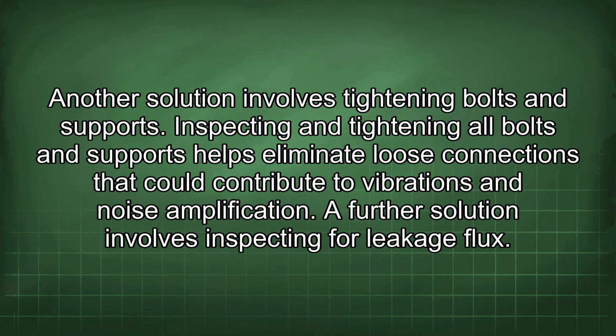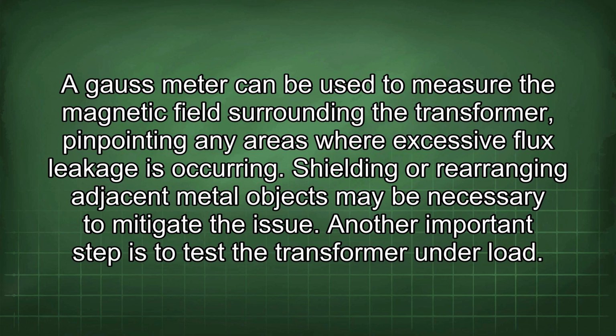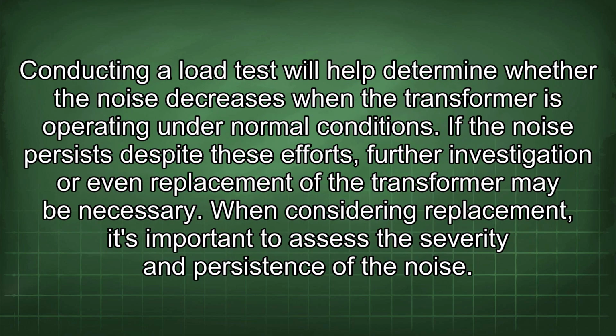A further solution involves inspecting for leakage flux. A gauss meter can be used to measure the magnetic field surrounding the transformer, pinpointing any areas where excessive flux leakage is occurring. Shielding or rearranging adjacent metal objects may be necessary to mitigate the issue. Another important step is to test the transformer under load. Conducting a load test will help determine whether the noise decreases when the transformer is operating under normal conditions. If the noise persists despite these efforts, further investigation or even replacement of the transformer may be necessary.